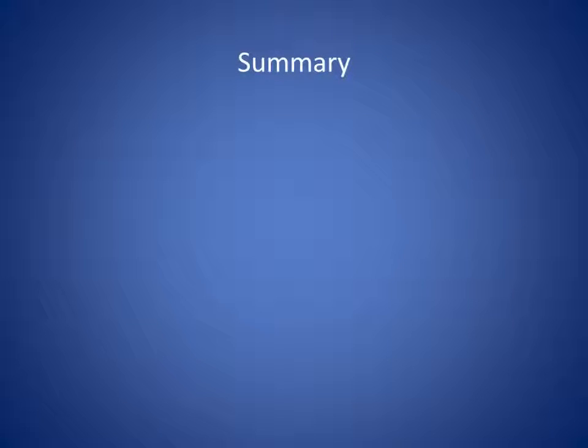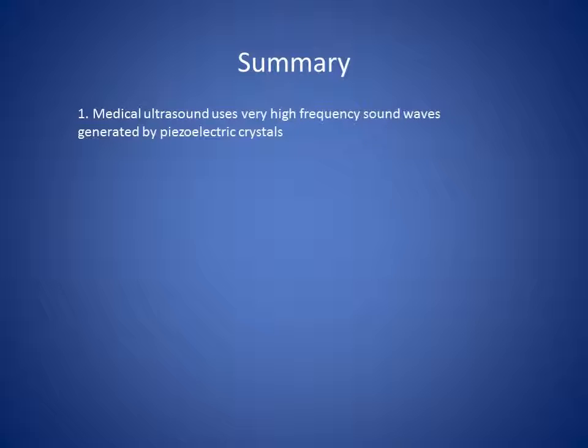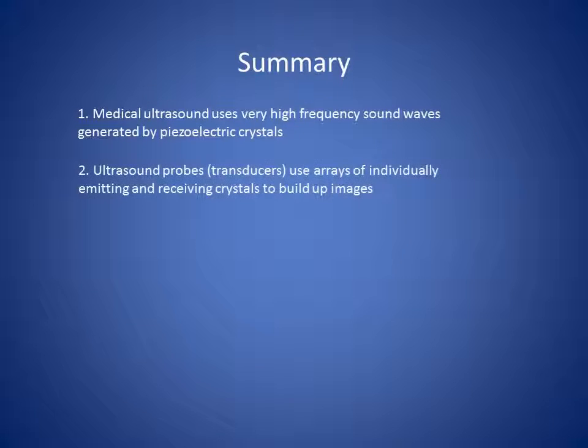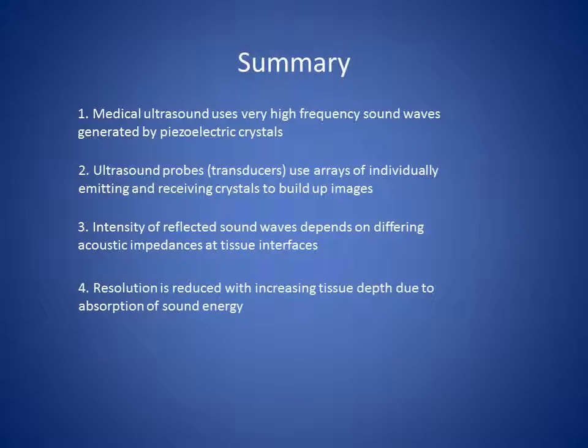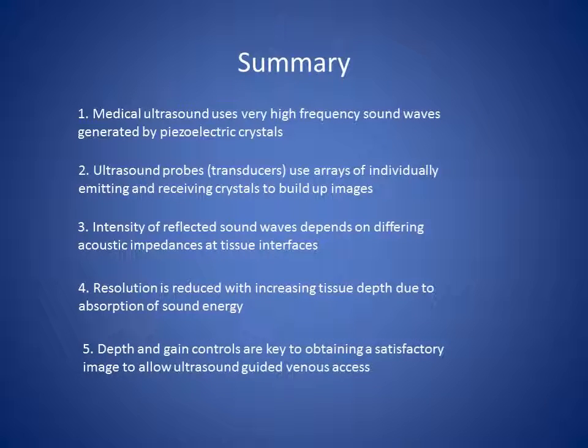In summary, medical ultrasound uses very high-frequency sound waves generated by piezoelectric crystals placed in a rapidly alternating electric field. Ultrasound probes, also called transducers, use arrays of individually emitting and receiving crystals to build up images. The intensity of reflected sound waves depends on differing acoustic impedances at tissue interfaces. Ultrasound resolution is reduced with increasing tissue depth due to absorption of sound energy, and depth and gain controls are key to obtaining a satisfactory image for ultrasound-guided venous access.